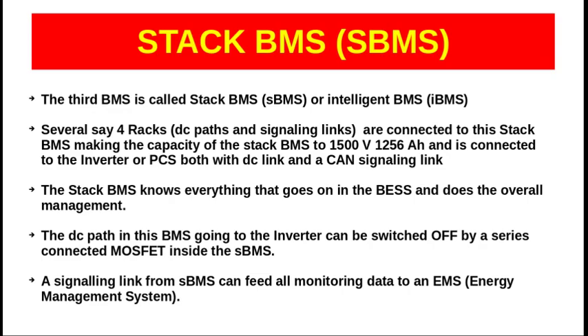Stack BMS. This stack BMS will be required if we connect more than one rack batteries in parallel. If we do not do the parallel connection of the racks, there is no need for this stack BMS. The rating of the stack BMS will be having the highest current and the highest voltage. For example, 1500 volt, and if we connected 4 racks, each of 314 amperes, the current rating will be 1256 ampere.